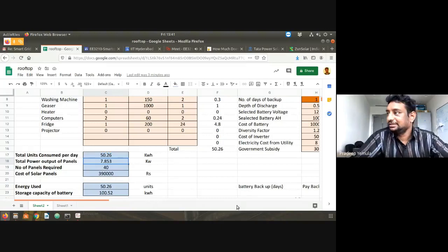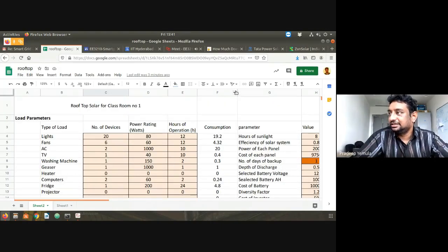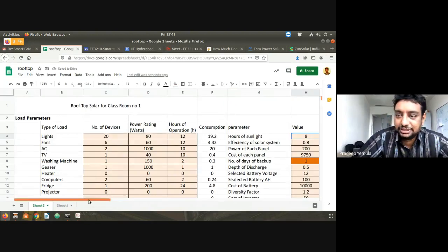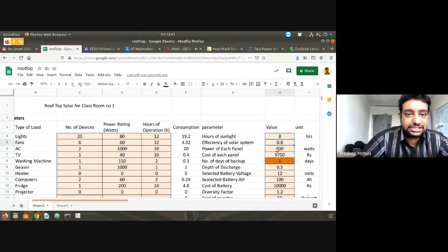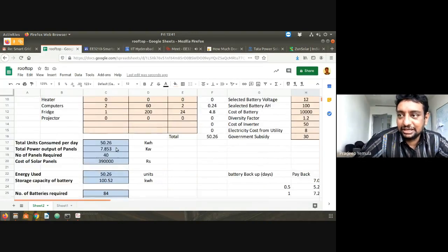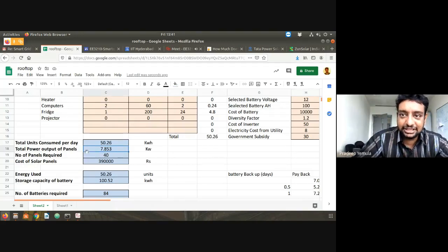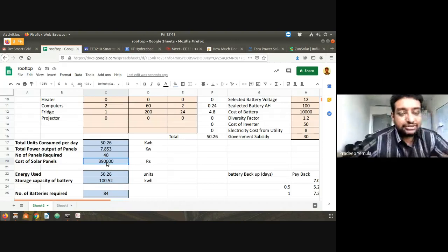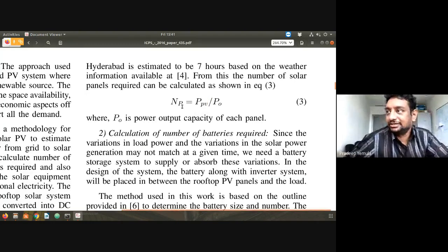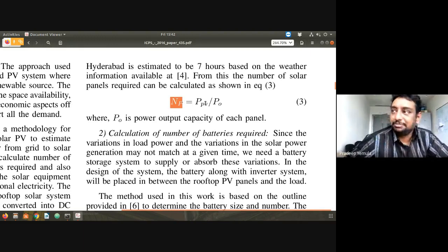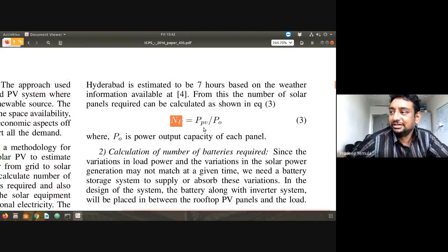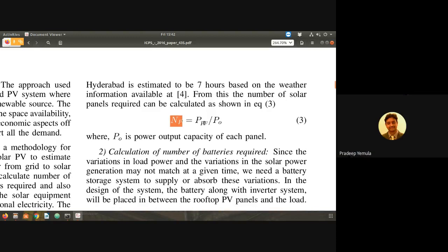Based on that, 7.8 kilowatts of capacity is needed. Each panel is 200 watts, so 40 panels are needed, and the cost of solar panels is 3,90,000 rupees total. The number of panels is total power divided by power per panel, and the panel cost is panel cost per unit multiplied by the number of panels.